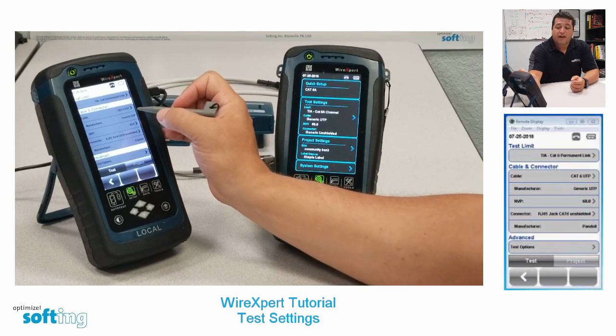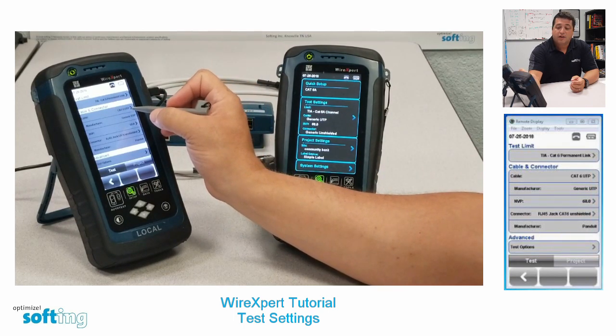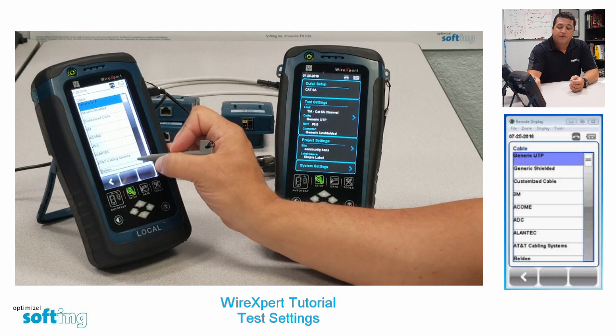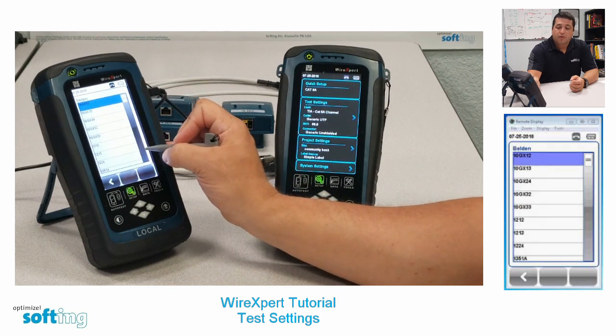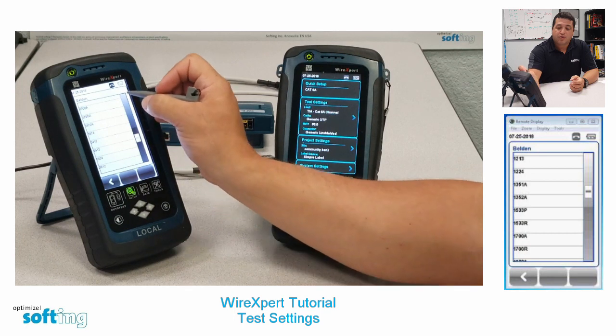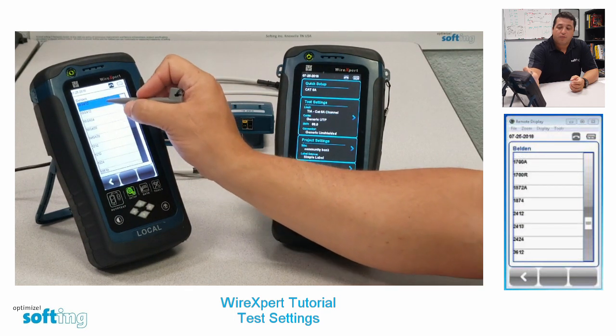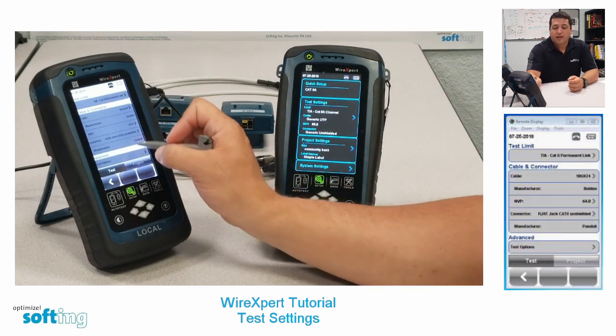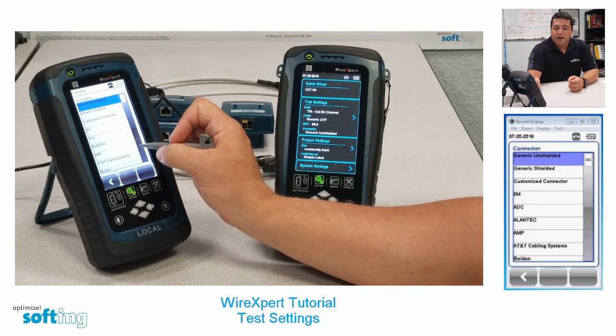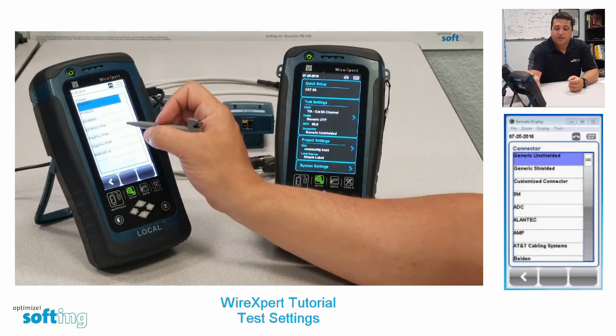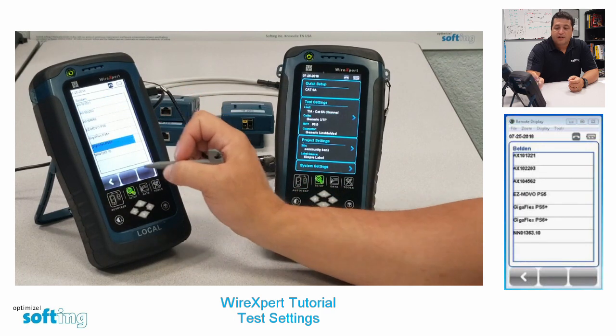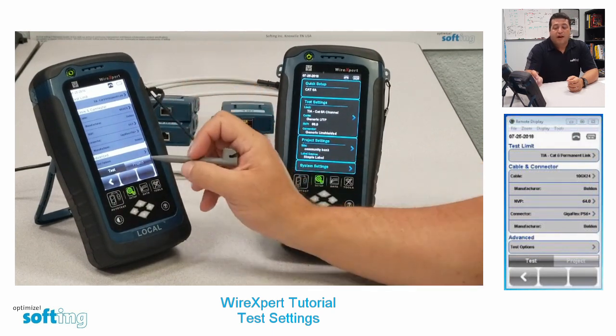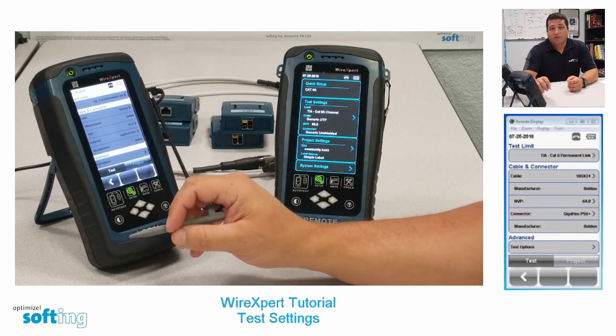We're going to use a specific cable manufacturer rather than a generic Cat 6 UTP. We'll select Belden — they make a lot of different cables — and grab their 10GX 24 cable. Then we'll choose a connector: the Belden Gigaflex PS6 Plus. Once those are selected, you are set for cable and have also chosen the correct test limit.